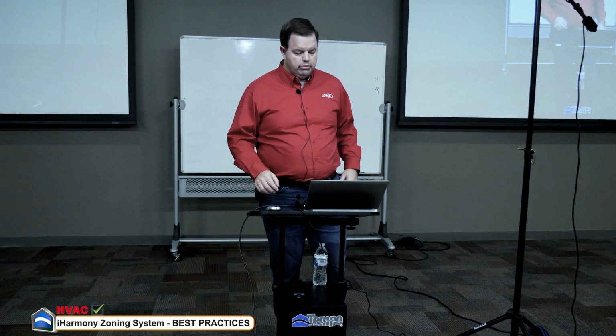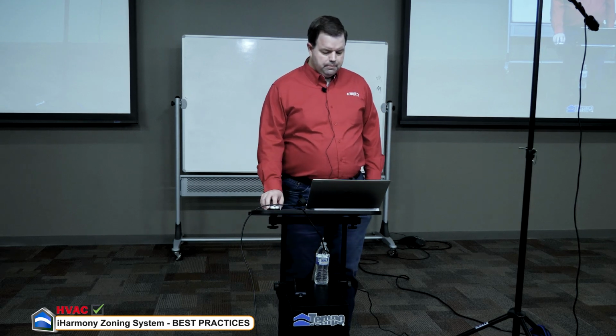Because you'll see that a lot, where even with the wires grounded, if you check with just R and C hooked up to the additional wires, you'll get some bleed over. You'll get some inductive voltage, basically just how a transformer works, where you might get 5, 6, 10, 12 volts AC on your DC communicating wires, and that's what can cause a lot of those issues. So that can be a real critical point here, separating the AC and DC voltage. Again, that's best practice for these.